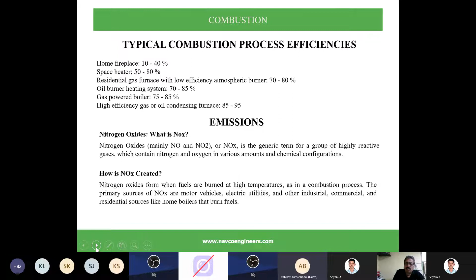How is NOx created? NOx, nitrogen oxide, forms when fuel is burned at high temperature in the combustion process. The primary sources of NOx are motor vehicles, electrical utilities, and other industrial, commercial and residential boilers that burn fuels. To arrest the NOx, there are two types of NOx reduction possible, mostly for power plants. Currently in India, our CPCB has introduced a DSOX and DNOx process. For DNOx, you have two types. One is SCR, selective catalytic reduction. One is SNCR, selective non-catalytic reduction.